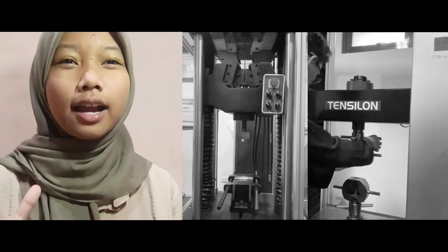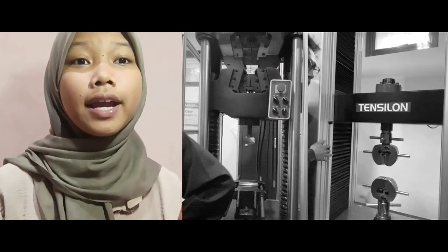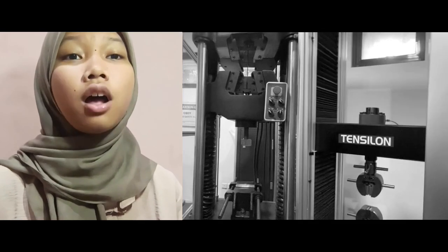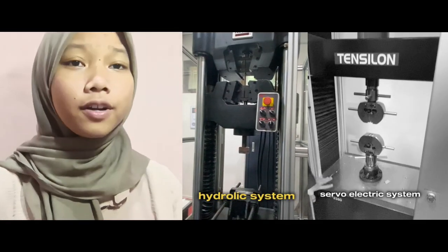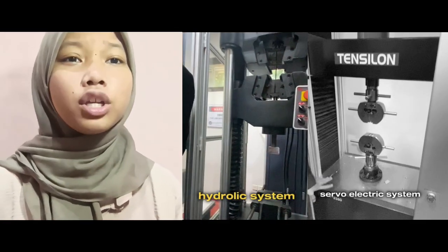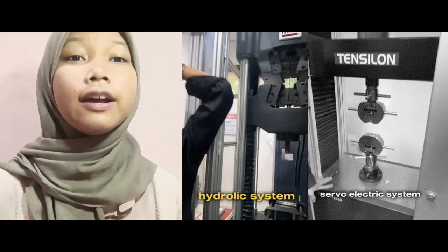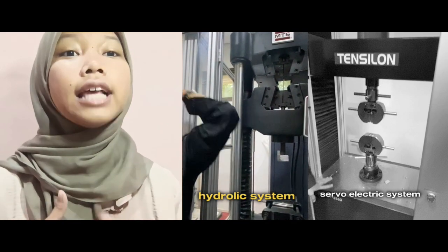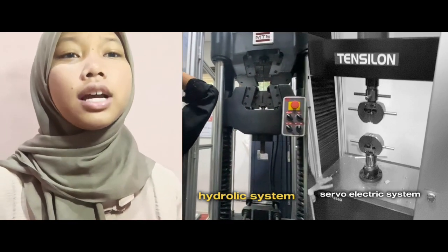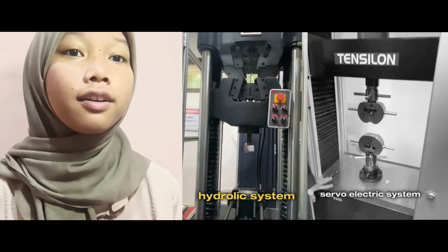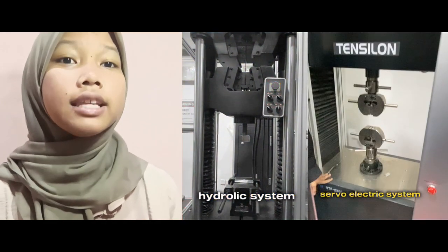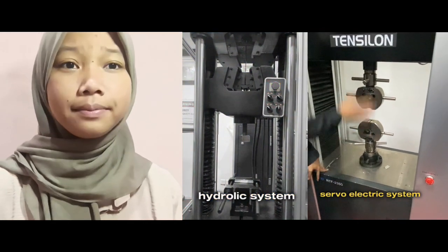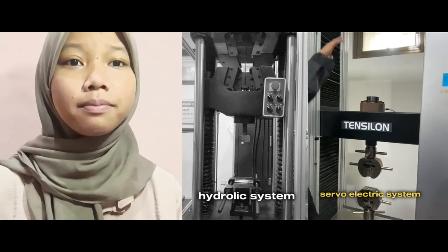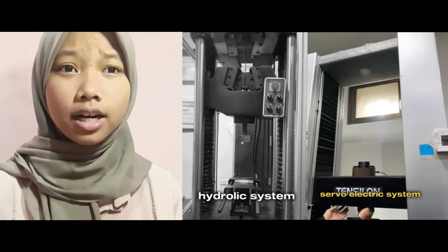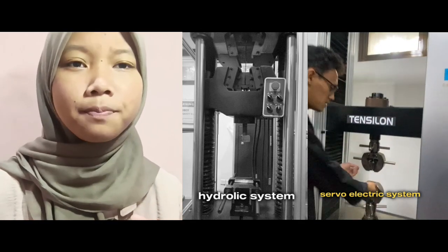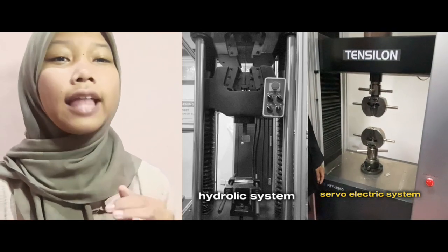Okay, about the types of UTM. There are two main types of UTMs based on the driving system. The first is the hydraulic system. It uses hydraulic fluid as the actuator. It usually has a large capacity, such as 30 tons, but the test curve tends to be rough. The second is the servo-electric system. It uses an electric motor.